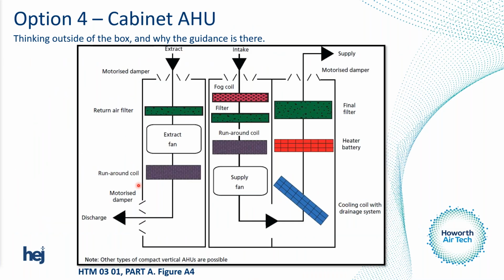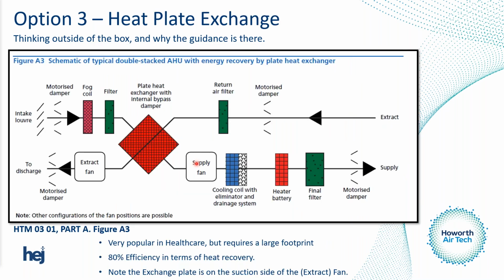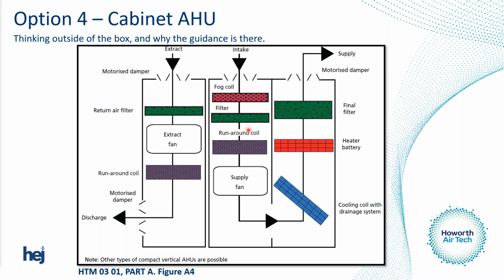A fairly new air handling unit in the industry is the cabinet air handling unit, and again, it's becoming popular. It has the least efficient method of heat recovery, but you can fit roughly two of those in the footprint of the other units. So in terms of refurbishments, they're a good option. There's a lot of manufacturers doing them now. AHS won an award for this at IHEEM last year, which is an excellent unit. They're all really good, there are some good units knocking about. So access from an engineering point of view, maintenance, it's all good stuff.